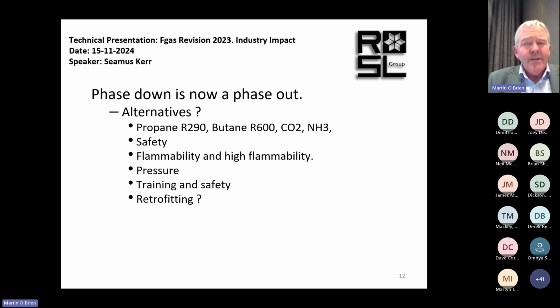CO2 isn't so bad yet because there's not so much of it around, but again it's a risky refrigerant. We're putting in plant rated to 130 bar — that's a lot of pressure when there's gas inside. We're working these systems at 80 bar, which is a lot of pressure. An air rifle that can kill a fully grown deer is only 34 bar in the piston, so imagine sitting with a plant at 80 bar.